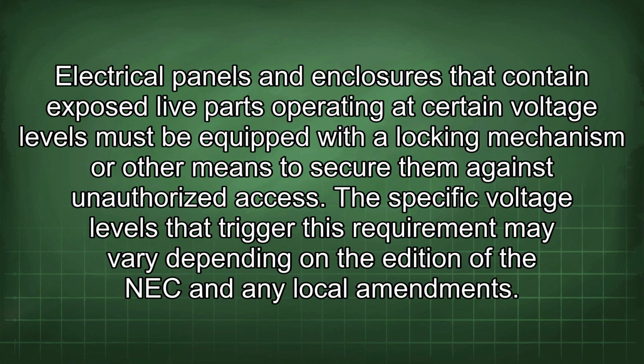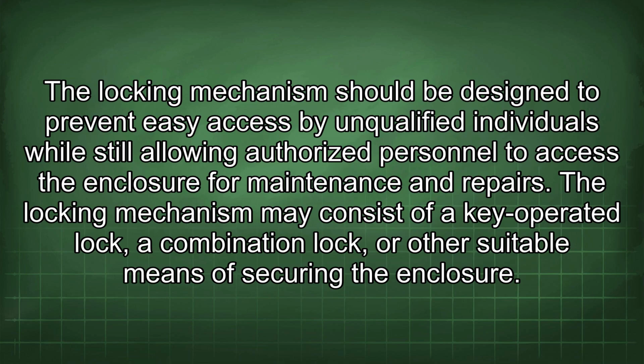Electrical panels and enclosures that contain exposed live parts operating at certain voltage levels must be equipped with a locking mechanism or other means to secure them against unauthorized access. The specific voltage levels that trigger this requirement may vary depending on the edition of the NEC and any local amendments. The locking mechanism should be designed to prevent easy access by unqualified individuals while still allowing authorized personnel to access the enclosure for maintenance and repairs. The locking mechanism may consist of a key-operated lock, a combination lock, or other suitable means of securing the enclosure.